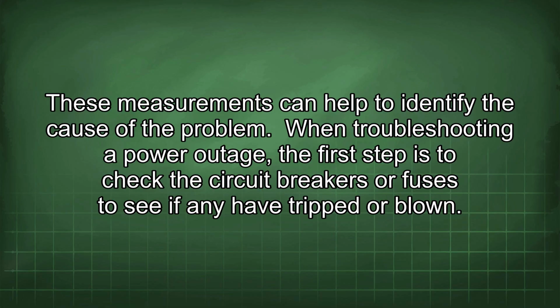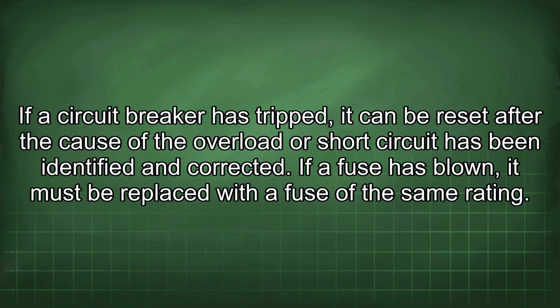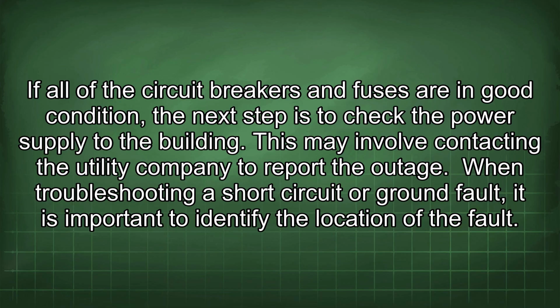When troubleshooting a power outage, the first step is to check the circuit breakers or fuses to see if any have tripped or blown. If a circuit breaker has tripped, it can be reset after the cause of the overload or short circuit has been identified and corrected. If a fuse has blown, it must be replaced with a fuse of the same rating. If all of the circuit breakers and fuses are in good condition, the next step is to check the power supply to the building.